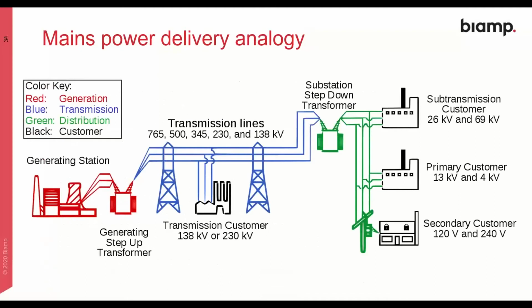So this shows you how the mains distribution works. You have a generating station where they produce quite a low voltage actually at the generation point. And then it's stepped up by a transformer locally. It's sent along the transmission lines at various different voltages, depending where in the world you are and the distance that it has to cover. And then at a substation, it's stepped down. And then at different substations, right down to the primary customer, it's up to about 4 kilovolts. And then locally to your house, there will be a secondary consumer transformer, which takes it down from 4 kilovolts, in my case, to 240 volts, for example. So in that way, we've increased the line voltage, reduced the current, so therefore we can use thinner transmission lines, but we've maintained the power that can be delivered to my house, for example. So that's exactly the same principle as high impedance or constant voltage loudspeaker systems.